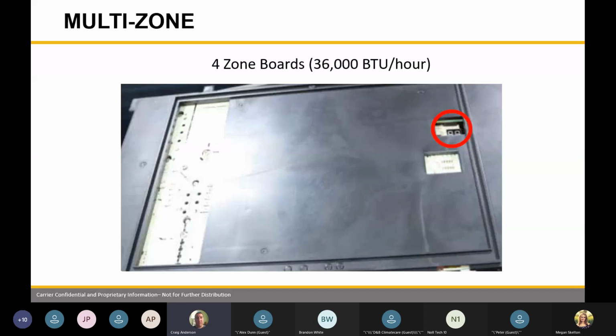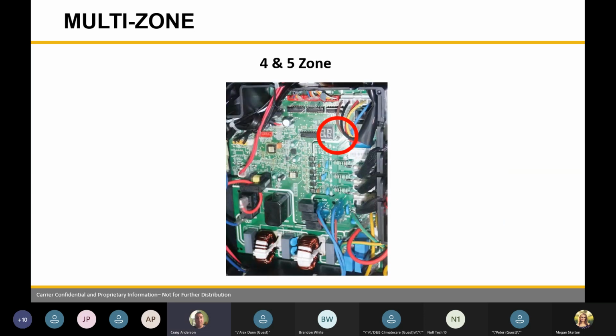Your 4-zone boards, when you open the unit, this is going to be similar to what it's going to be looking like. You're going to have a little sight glass there where you can read your error code as well. 5 zones, your boards are going to be upright. It's going to have a little display like that as well where we can read that code on the outdoor unit. So it's a nice thing. We have codes on outdoor, we have codes on indoor. We'll be able to decipher by our troubleshooting charts where we need to look and what the unit is doing.